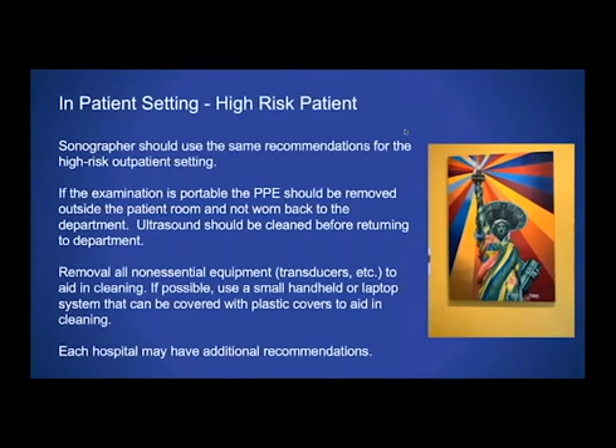Again, you need to clean the machine before you return to the department. If you need to set up in scrubs, use whatever recommendation is being used at your hospital. And I think a couple of the other authors have said again, remove all non-essential equipment and transducers; everything you have on the machine needs to be cleaned. So the less stuff you have, the less you're going to have to clean, and the less likely you are to leave some contamination. Again, using a small handheld or laptop system that you can cover with plastic covers will aid in cleaning, and each hospital may have additional recommendations.